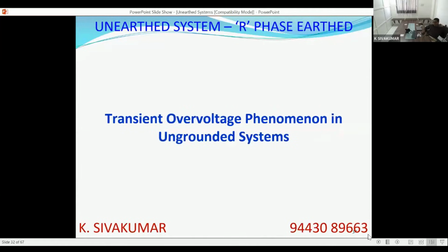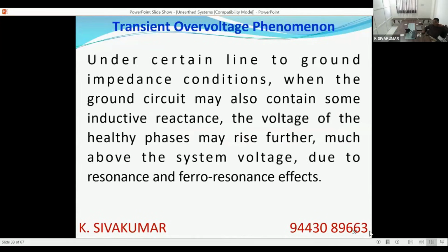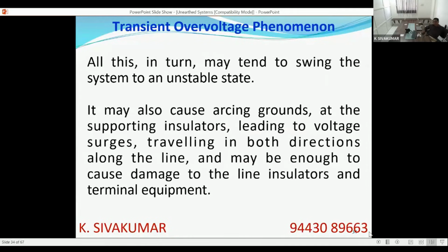So the biggest disadvantage is that during an earth fault, transient overvoltage happens in an ungrounded system. Let us analyze what happens. Under certain line to ground impedance conditions, the ground circuit will contain inductive reactance and the voltage of the healthy phases may rise further. That is, it may even go to 5 to 6 times or more. We call this condition resonance and ferroresonance. We will see how it goes. Also, this may tend to swing the system to an unstable state. There will be arcing grounds because the voltage to the earth keeps on rising. There will be a tendency for the arc to strike between the phase and the ground or the phase and the earthed conductor. So this will lead to the failure of support insulators and the equipment connected to the system, line insulators and terminal equipment. There were reports of failure of equipment, insulators and all because of this arcing ground.